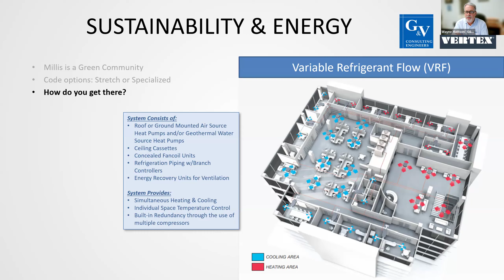And I throw this slide in here because geothermal is talked about a lot, and I just want people to understand how geothermal works. I don't presume that everybody understands HVAC or our system. So when we talk about geothermal, what that really means is you use the ground as a heat sink. So in the summertime, heat from the building is rejected through a heat pump cycle, and that heat is rejected into the ground. And then in the wintertime, when you want to heat your building, the ground has a very stable temperature that ranges anywhere from 50 to 60 degrees. You extract that heat out of the ground through a heat pump, and that's rejected into your building.